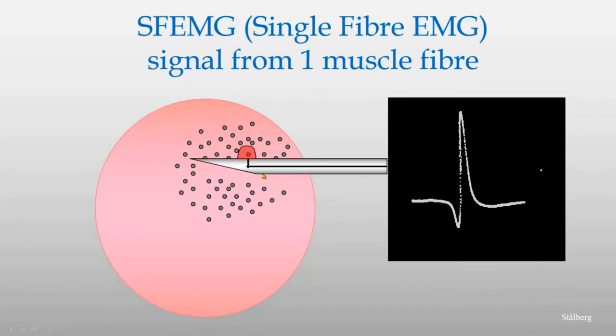Therefore a needle electrode was constructed with a much smaller recording surface. The selectivity was further increased by changing the amplifier filters so that signal components of low frequencies — namely those generated by more distant fibers — were restricted. All signal components below 500 Hz were suppressed. Now we get sharp signals with amplitudes from a few hundred microvolts up to many millivolts, depending on the position of the electrode in the muscle.